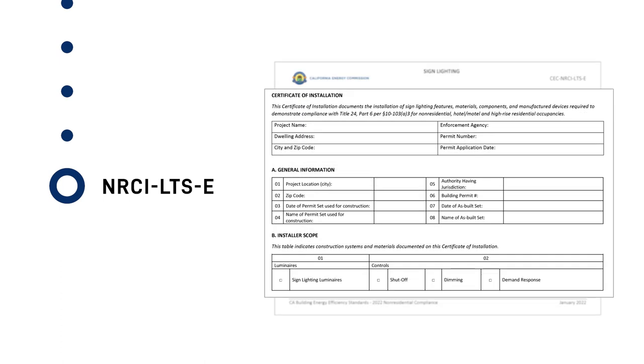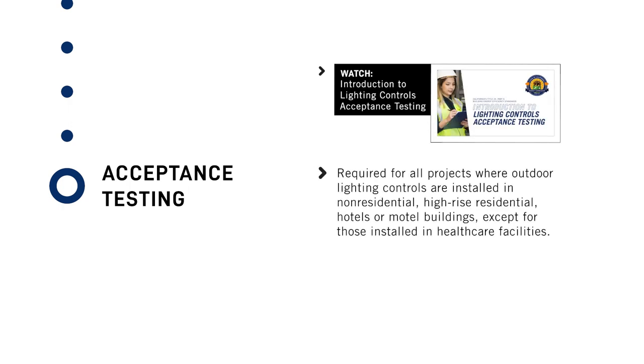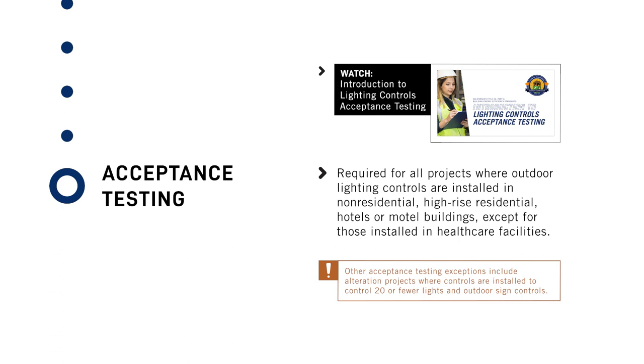Acceptance testing is required for all projects where outdoor lighting controls are installed in non-residential, high-rise residential, hotels or motel buildings, except for those installed in health care facilities. Other acceptance testing exceptions include alteration projects where controls are installed to control 20 or fewer lights, and outdoor sign controls.